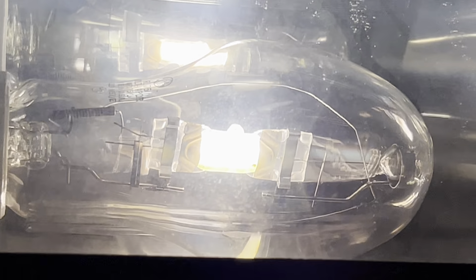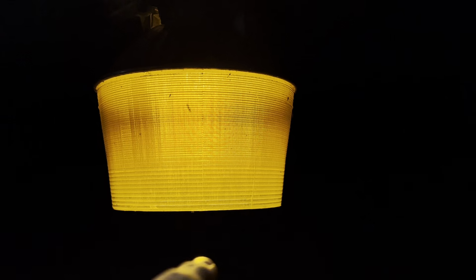This is probe start metal halide. You can see that big resistor right there, and that circuit. That's a probe start lamp, meaning the ballast builds up enough current to start the arc in that tube. There's no igniter like there is in high pressure sodium. This requires a 4,000 volt strike or pulse to start.